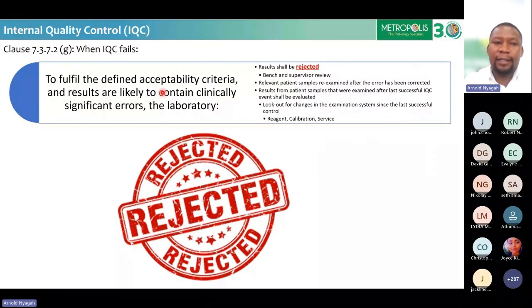Then the other recommendation in these clauses is that you need to re-examine the sample. That is, if the rejection was appropriate, you need to re-examine the samples after the error has been corrected. Then the results from patient samples that were examined after the last successful IQC event shall be evaluated. What this software has assisted us in doing is checking for any changes that happened for that particular test during the QC, because this is recorded in the action logs on Unity real time, whether it is a reagent change, calibration, or a major service.